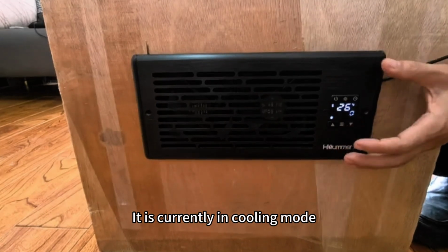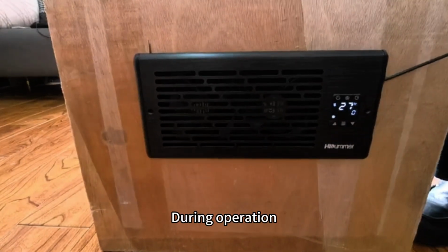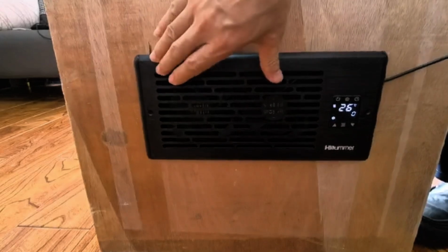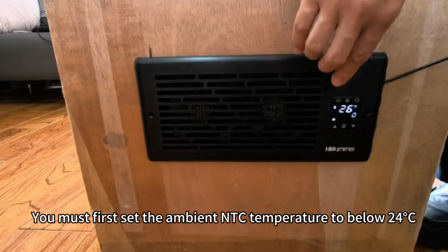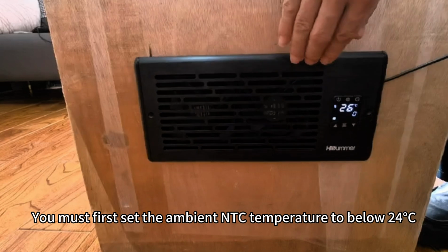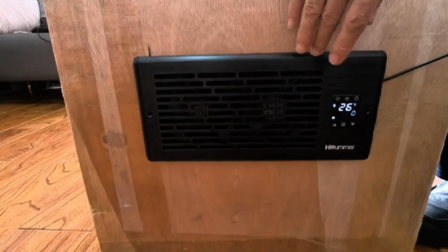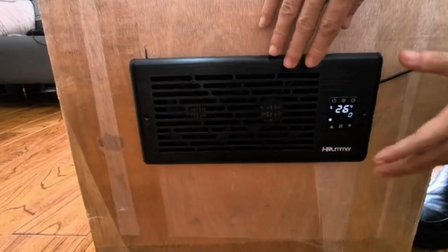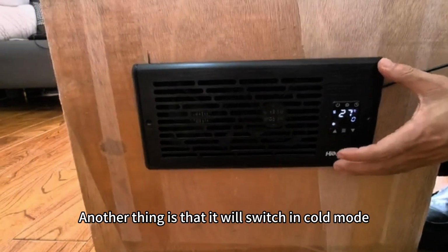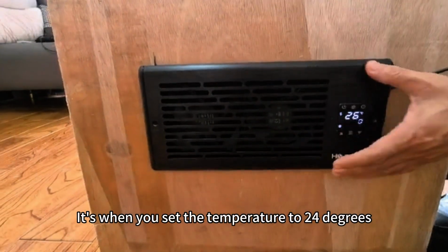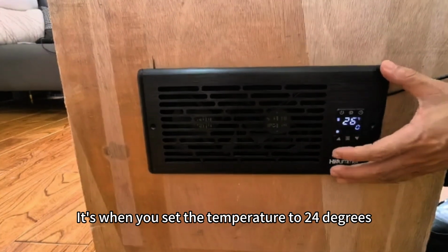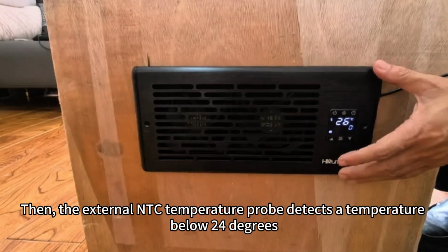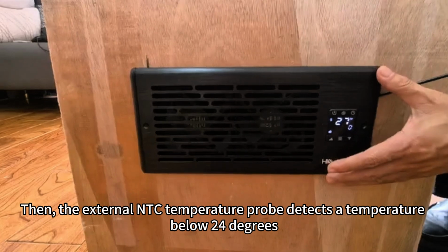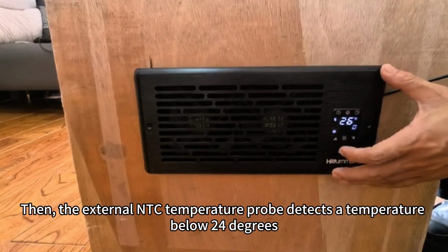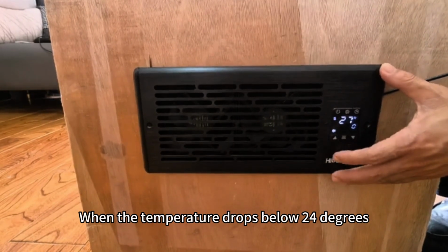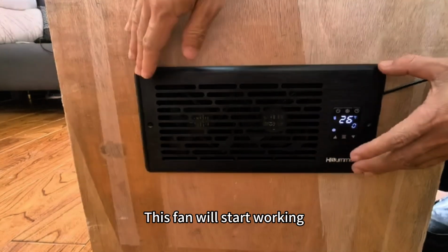It is currently in cooling mode. During operation, you must first set the ambient NTC temperature to below 24 C. Only then will it work. Another thing is that it will switch in cold mode when you set the temperature to 24 degrees. Then, the external NTC temperature probe detects a temperature below 24 degrees. When the temperature drops below 24 degrees, this fan will start working.